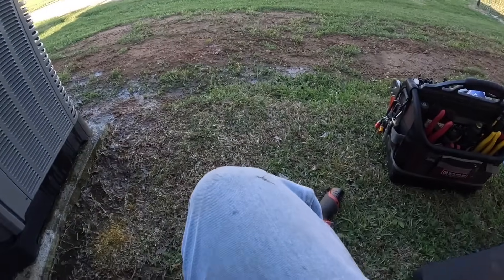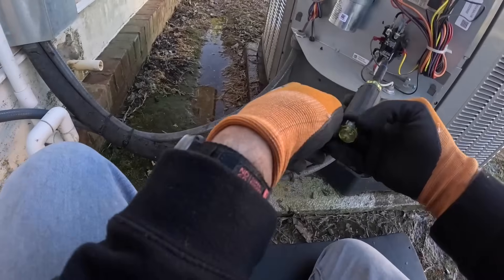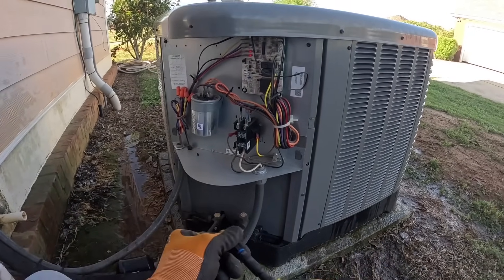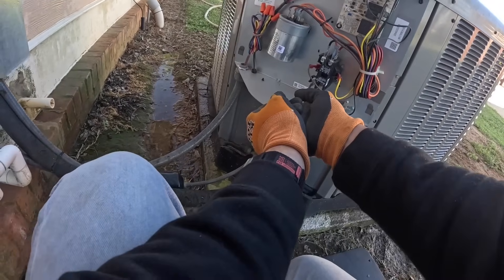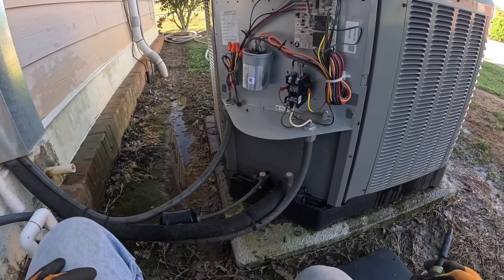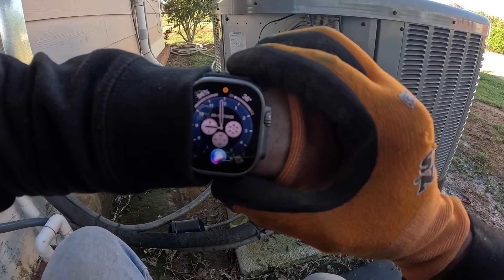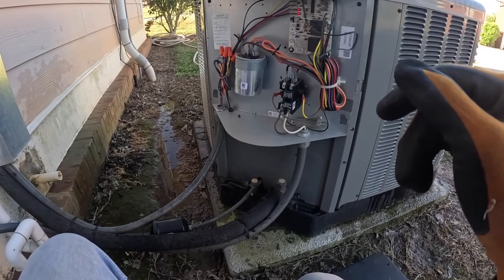One thing I want to check over here is the lugs on this. We're good on that. Let's hook up and get ready to check pressures. I'm not running it in cool - it's just way too cold. Right now that says it's 36 degrees. So we're going to be checking pressures in heat.